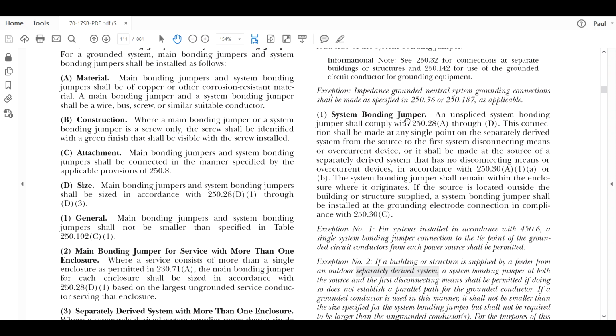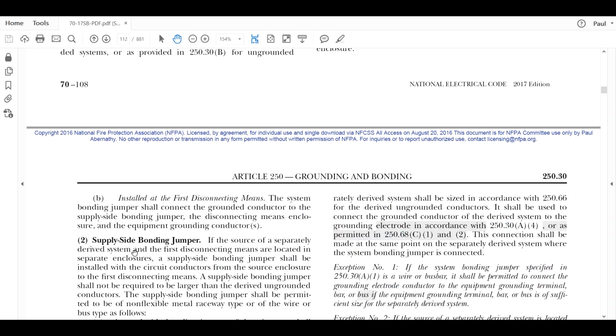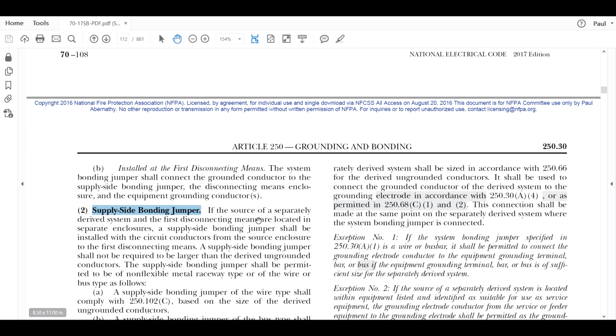All right, so when we get to the system bonding jumper, we'll look right here. But right now, we're doing the supply side bonding jumper right here. Now remember our graphic. We have a transformer and we have a separate panel that has the first disconnection means in it. If the source of the separately derived system and the first disconnection means are located in separate enclosures, which in our case they are, it says a supply-side bonding jumper shall be installed with the circuit conductors from the source enclosure to the first disconnection means, and we did that.